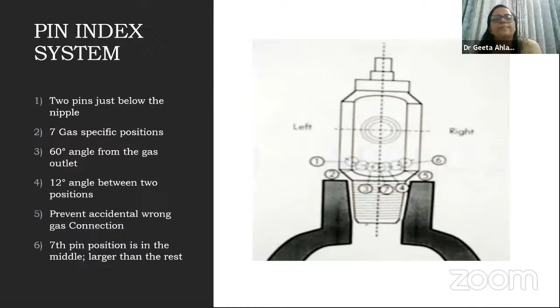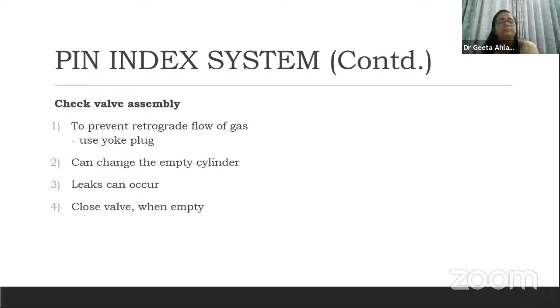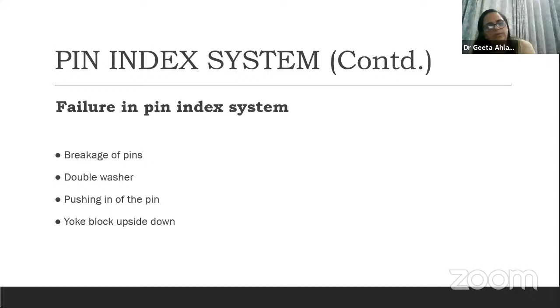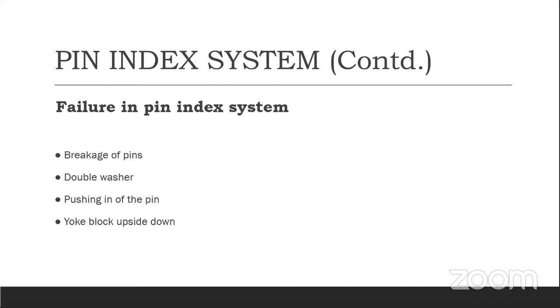So there is a check valve assembly to prevent the retrograde flow of gases. You can change the empty cylinders. However, leaks can occur, and you can close the valve when required. However, it can fail if the pins are broken, if there is a double washer, or the pins are pushed inside, or the yoke block has been put upside down.